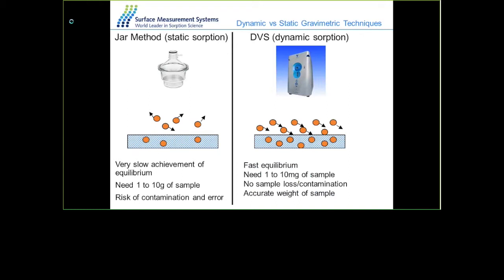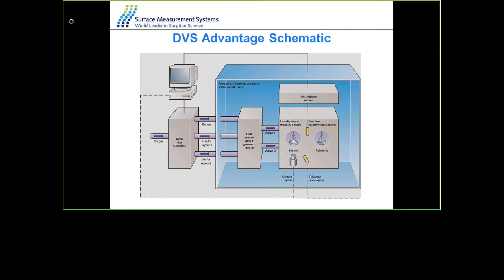Only a small amount of sample in the milligram range — sometimes as small as one milligram — can be used. The sample stays in the sample chamber, so there is no risk of contamination or sample loss. A microbalance with 0.1 microgram accuracy is used to monitor changes in the mass of the sample.